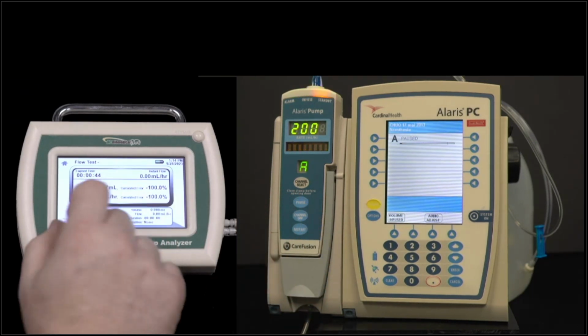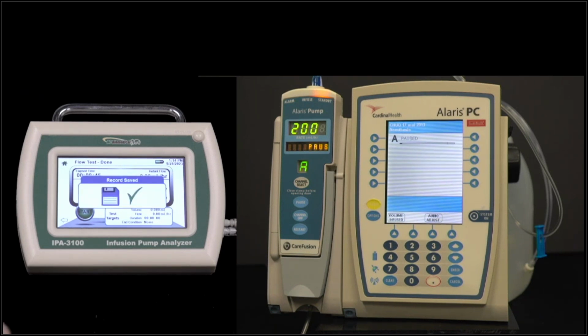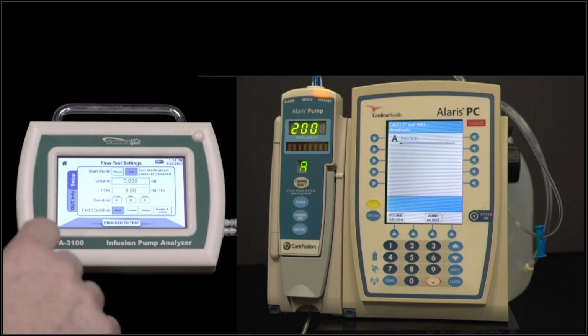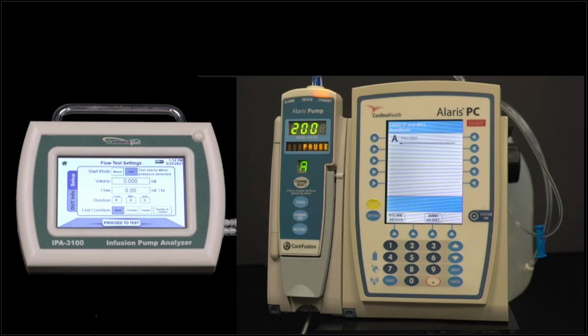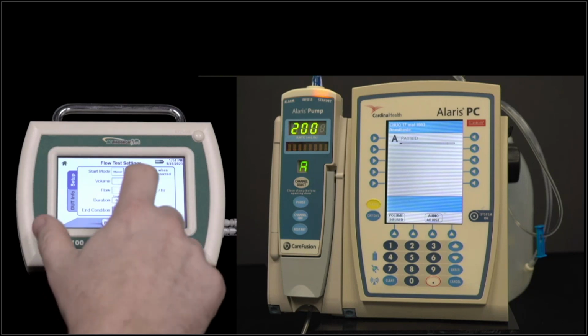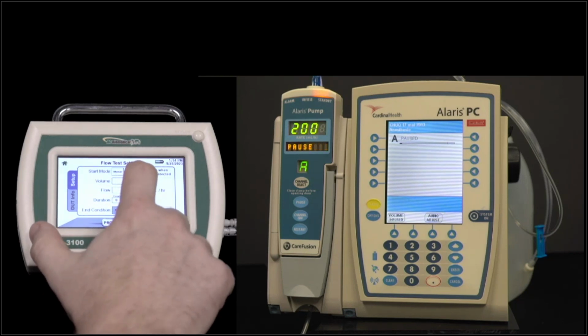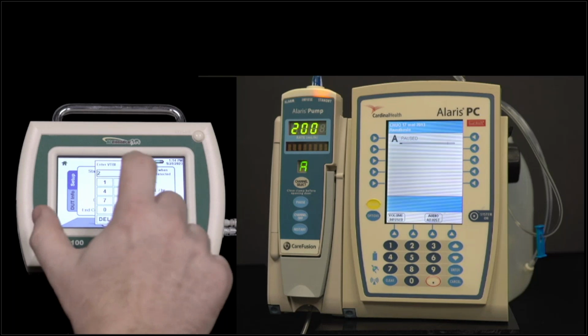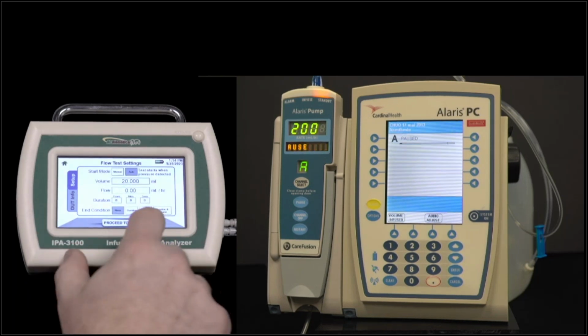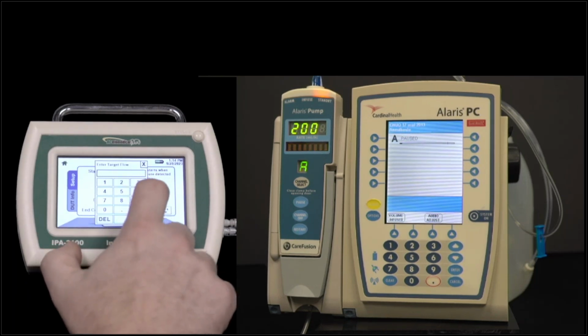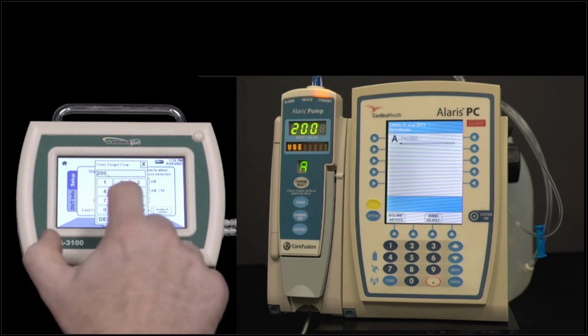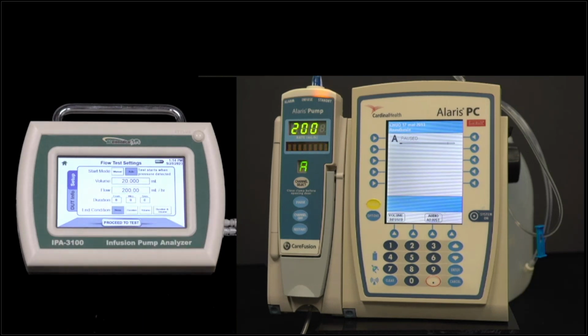Now I'm going to go in and show you. So now it's saved that record. I'm going to go back and say, what if we really want that information? I want to know, what's my percent error? How accurate is this pump? Is it performing like it should? So I can go into the settings here, and I could say we're going to set for 20 milliliters, and our flow rate is going to be 200 milliliters per hour. Now it has values to compare against.